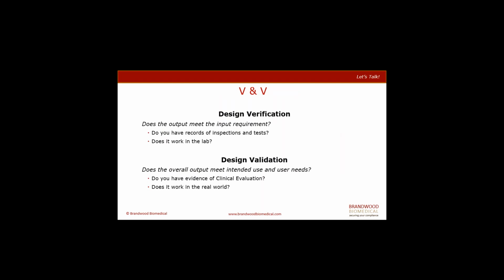Design verification and design validation. So basically, does the output meet the input requirements? Do you have records of inspections and tests? And does it work in the laboratory? That will define your verification. But most importantly, the records of the verification activities undertaken is critical when looking at the project to move on to the next stage, and also at potentially inspection or audit time. And the same applies for validation.